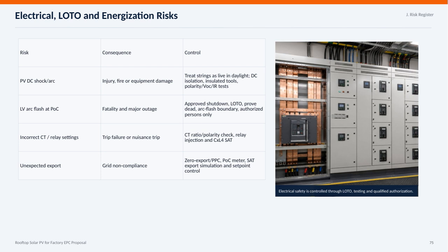At the point of connection, low-voltage arc flashes pose a severe risk of fatality and major outages. This is managed by implementing approved shutdown procedures, strict lockout-tagout protocols, proving the circuit is dead before work, enforcing an arc flash boundary and limiting access to authorized personnel only.